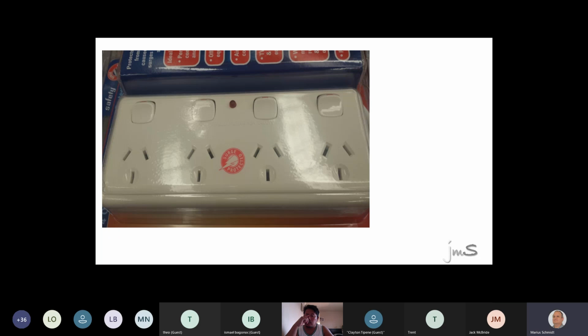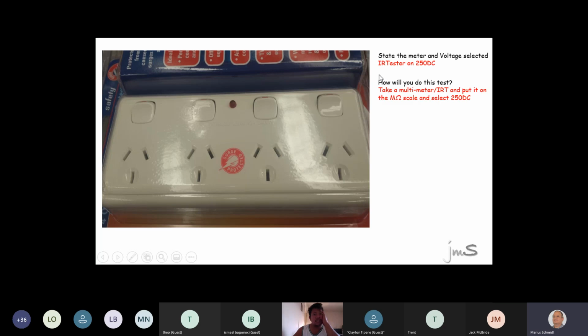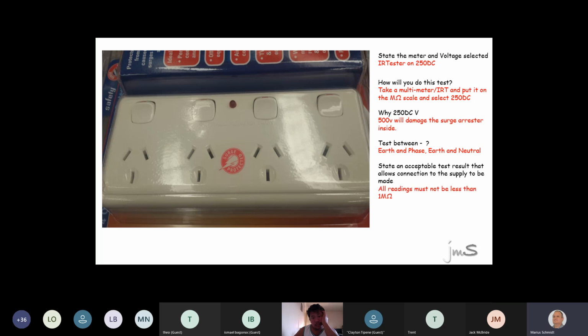You know how many times I've seen students take a multimeter, they measure between earth and phase and say, look, it looks good. Yeah, right, everything looks good. Right, guys, when you see an instrument which has a little surge arrestor there, alarm bells should go off and say to you, when you see this, you cannot use 500 volts. You're going to use how many volts? 250. Right, guys? Everything is the same. What will 500 do to that part of the installation? Damage it. Right, guys? Very important. All readings are the same. The only difference is we'll use 250 instead of 500.